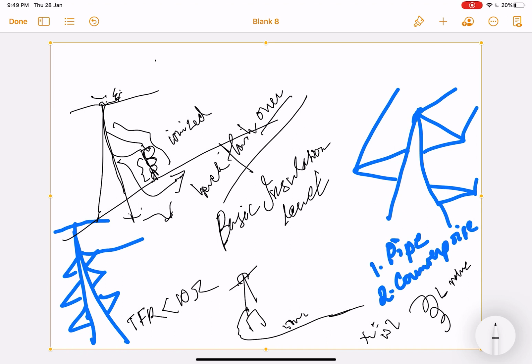Another thing we can do to protect our system is additional earthing. Apart from the bottom earthing which we have done, we can also do additional earthing, where from the earth wire at the top, we take one additional wire across the tower and earth it to the ground. Again, at the ground level we should ensure proper earthing. This is an extra wire apart from the tower body, an additional path, so we call this additional earthing, or shield earthing, because this earth wire is also called shield wire.